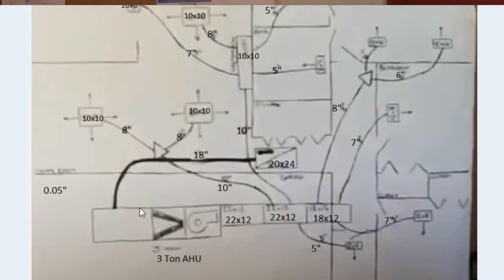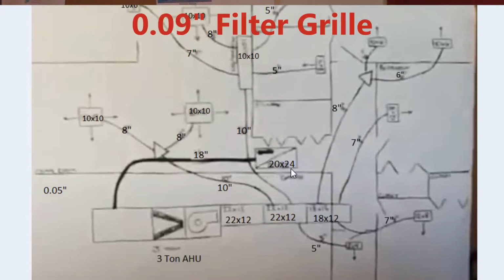Okay, now we're going to look at the return. There is a pressure drop associated with this filter grill itself. Again, you'll go right back in that book and try to figure out which 20 by 24 filter grill you're using. What is the drop associated with the grill itself? And you will add that into the equation. For this one, I found a 20 by 24 ceiling filter grill or filter rack at a 0.09.